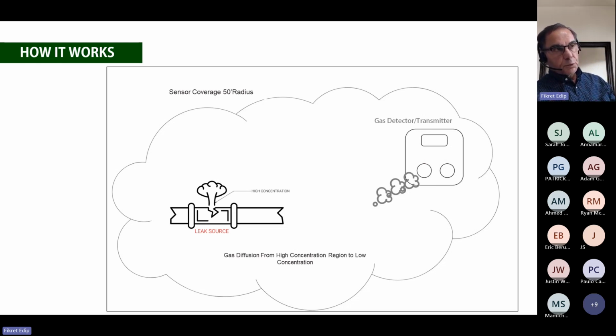Now, in some applications where you need to reduce that 50 feet radius, such as a chiller room application, or you're in a warehouse application where you have so many obstacles and shelves and all that, then you need to add more sensors in that location. And that comes to, when we receive a project in mechanical drawing, we look at the layout and we recommend it. But my point from this slide is, how does the sensor sense that gas? Equate that to somebody walking into a room wearing a heavy perfume, standing in the corner of the room. It doesn't take too long before the other person on the other side of the room can smell it. And that is the diffusion from high concentration to low concentration.